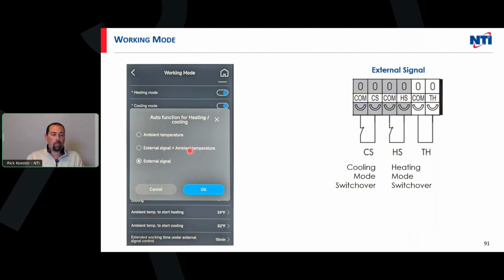An external signal with ambient are probably going to be the most common that we do see. I feel the external signal is probably going to be the most popular. What that basically means is that any dry contact I bring in to cooling switchover or heating switchover, that's what's going to drive the machine to turn on and run. So if I had a third-party relay, whoever you sell, there's a bunch of them out there. Whoever's relay you're using, if I run their end switches back to this control and right to these terminations here, anytime one of those zones calls, that relay is going to control whether it be a zone valve and circulator or just a circulator. It'll turn them on and it'll function right from there.